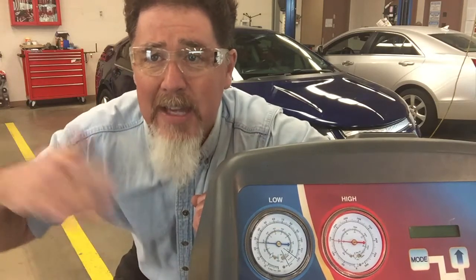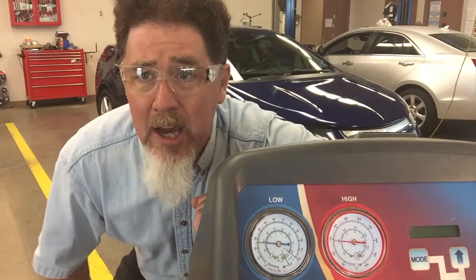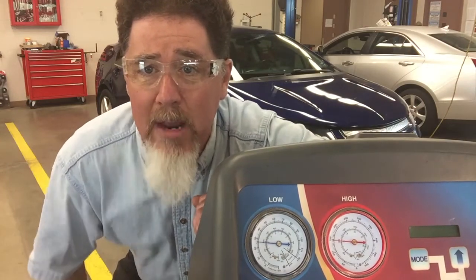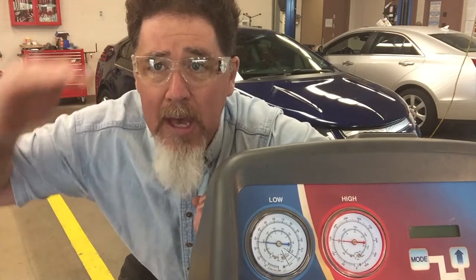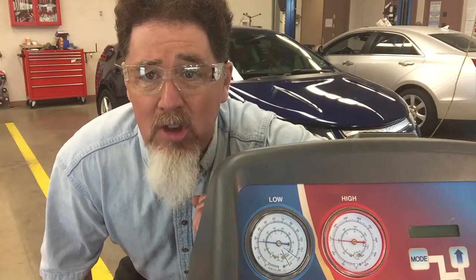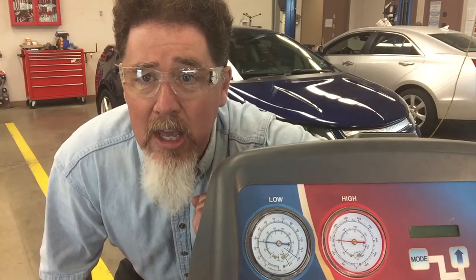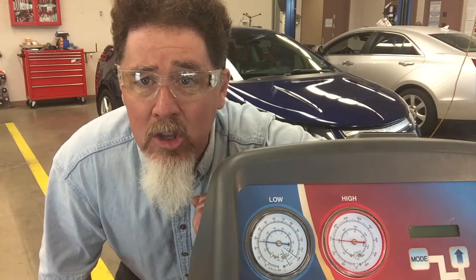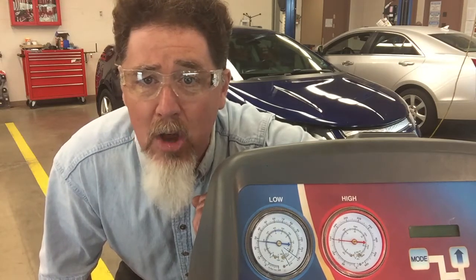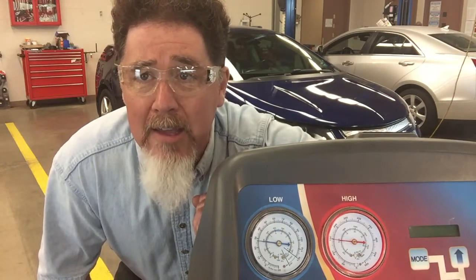It will give it an additional heat load. And so if the system is cycling off and on because there's just no heat load in the system, that's another way to be able to get your pressures up a little bit. So it stops cycling a little bit, and so we can slowly see the gauge readings creep back up again to around 30 PSI on the low side, around 150 on the high side.